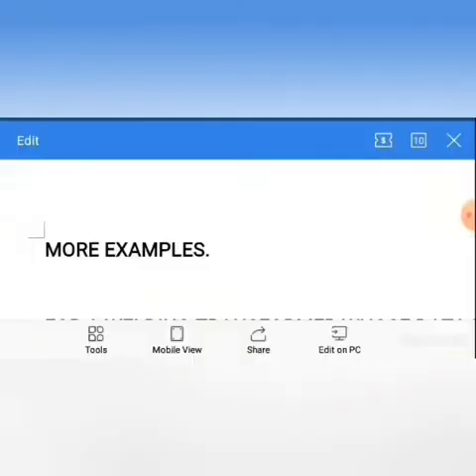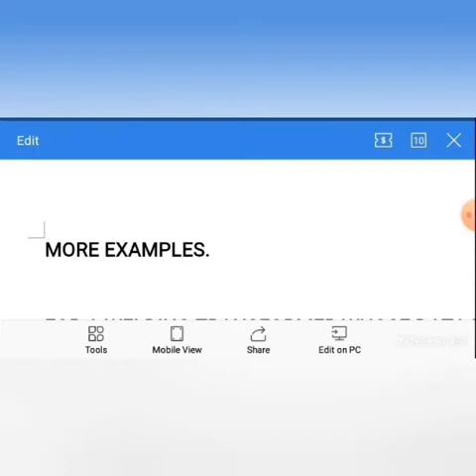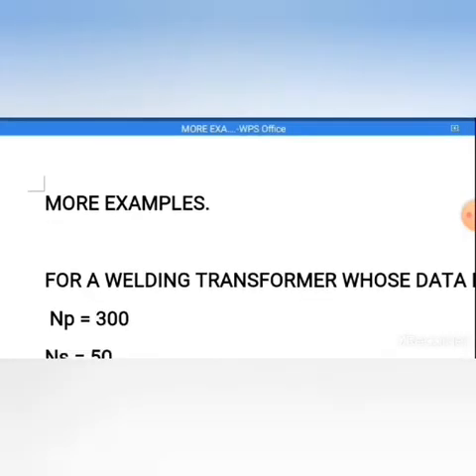We have more examples to understand how to find the specification or rating of a welding transformer. Most times the ratings of some welding transformers might not be there — they come with no name plates. So if you meet such a welding transformer, you need to do your calculations to find its specifications, which will guide you on the measures to take to put the transformer back working.